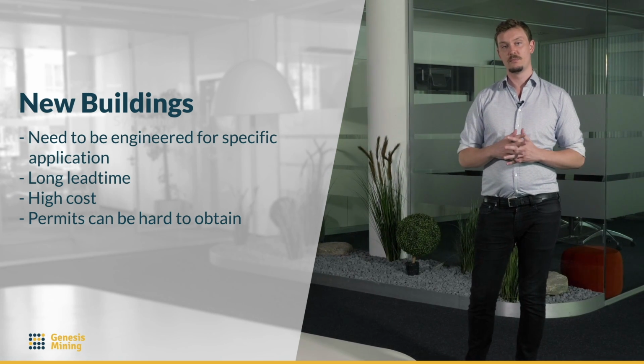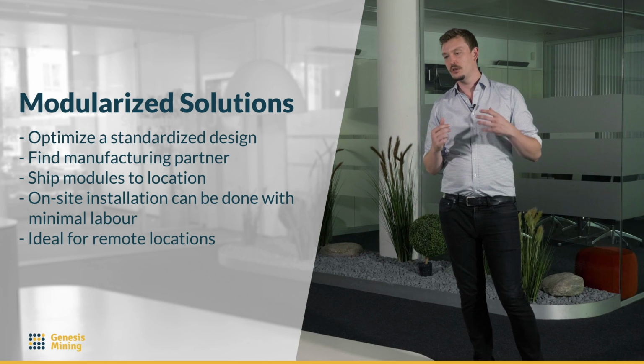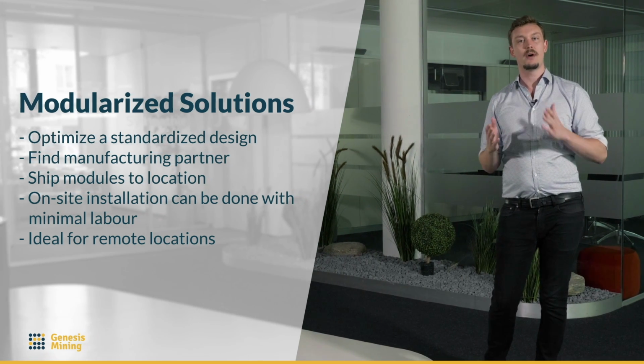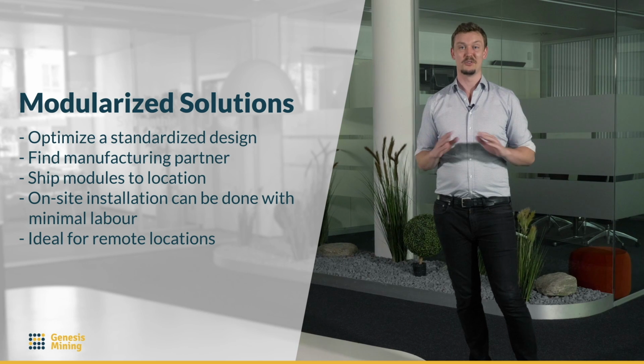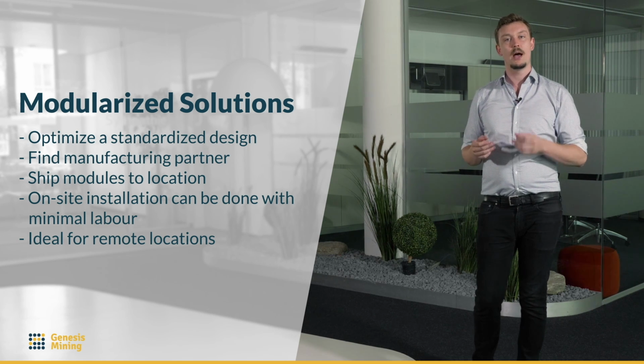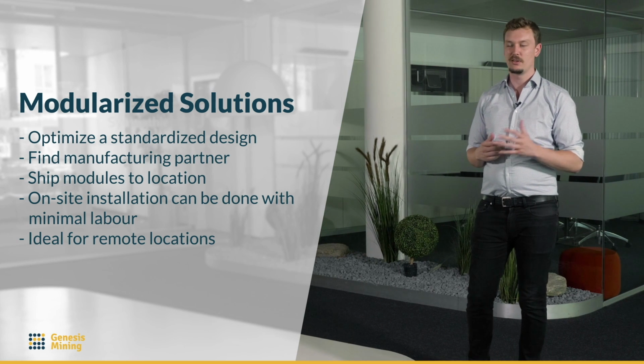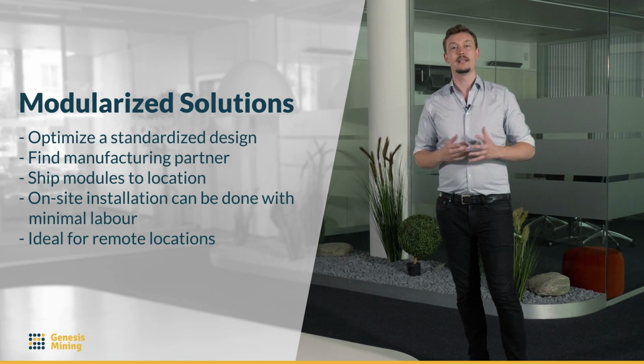The best way to go forward with this is to have modularized solutions. You don't want to have a fresh solution for every new site that you want to build a data center on. You want to have a modular solution where you've perfected one mining module, piece of hardware, and you found a manufacturing partner for manufacturing these modules quickly and securely and with quality control. Just ship them to the site that you want to install them to, and with minimal on-site labor, install the finished modules on site. I'm saying modules because it's not always containers, but I think containers are a really good example.